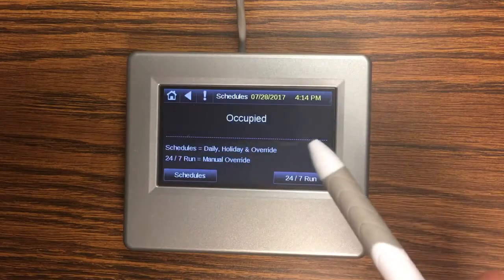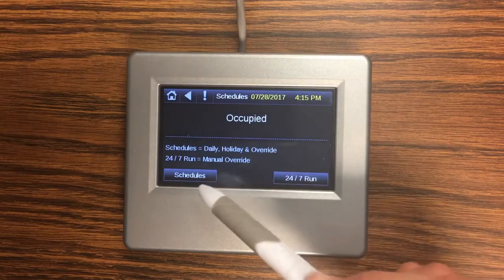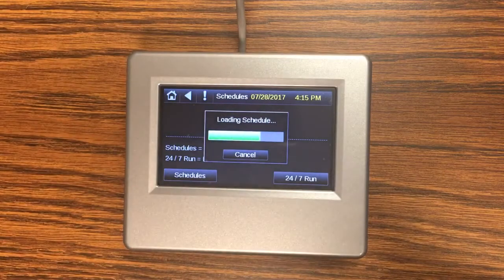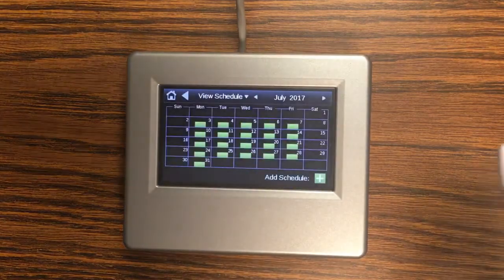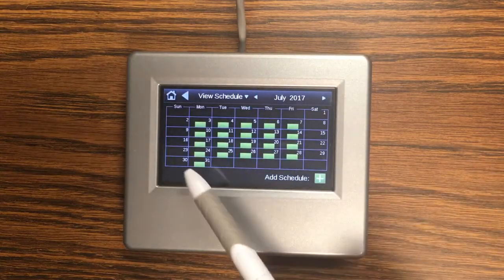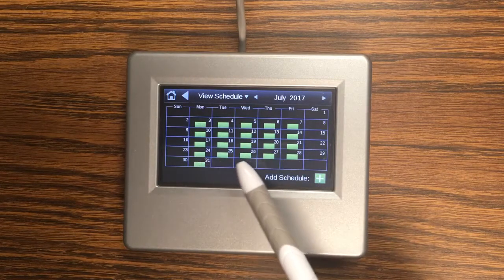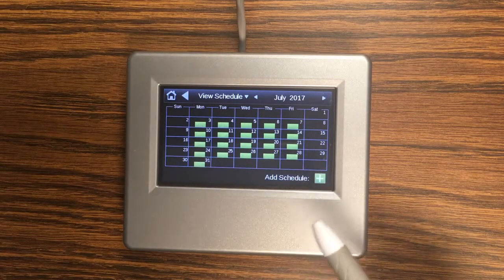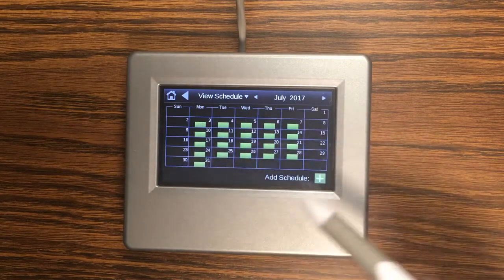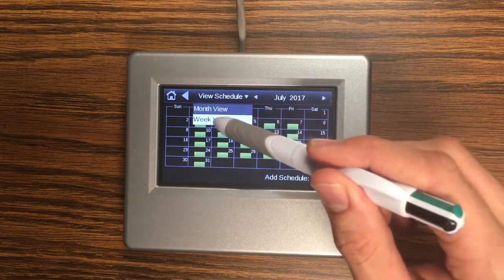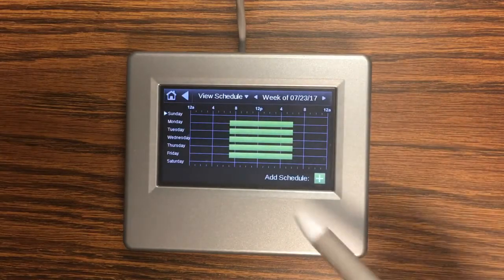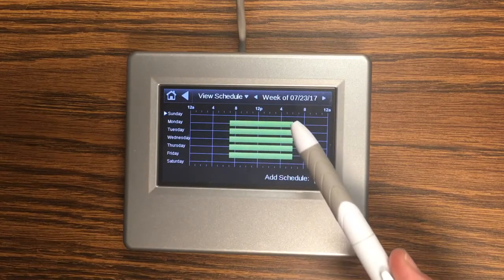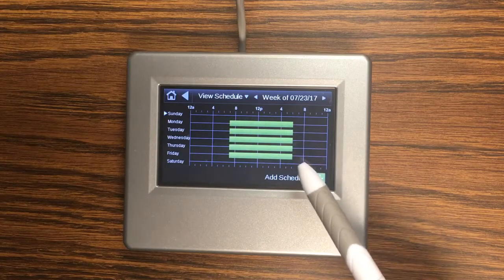If you do want to have an occupied and unoccupied schedule you can go to schedules and it's going to bring up a calendar and these green symbols are telling us that we have occupied time set up in the schedule for all of these dates. Now this calendar view is kind of small so normally I go to the week view and you can see that we're occupied between 7 a.m. and 6 p.m. five days a week.